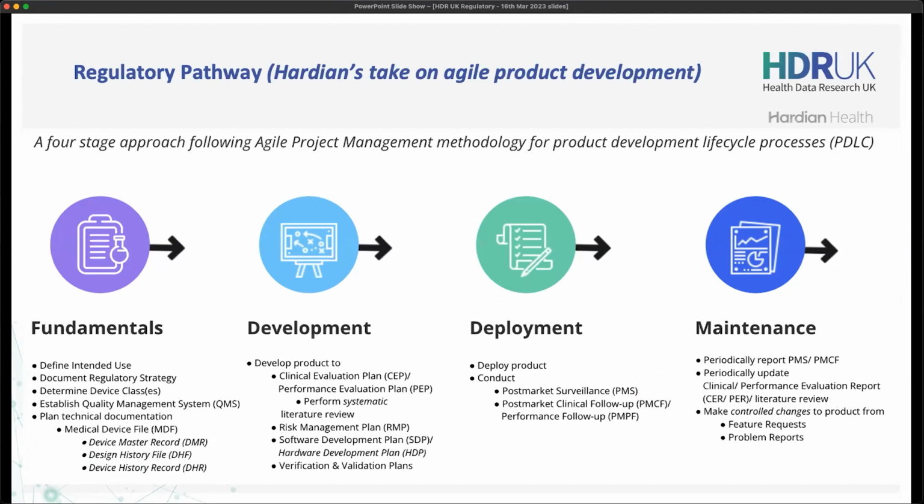So we start off with the fundamentals. The most important one, which Mike touched on, and we're going to have a case study later today as well, is the intended use. What does your device actually do? What are the intended indications? What are the claims? What are the use environments? Is this going to be used by professionals? Is this going to be used by lay users? If it's going to be used by professionals, do these people have the appropriate training? If it's going to be used by lay users, do these people need to be trained? Do your instructions for use need to be a little bit clearer?